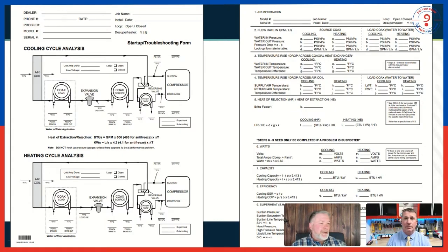As you're going through this chart, the very first thing after you put the model and serial number in is your water flow. So we ask our technicians, before they call tech support, fill this page out 1 through 5. Don't put your gauges on—just basically, you've got a pocket thermometer to give you water temperatures, and you've got a pressure gauge. Non-invasive, just the basics.